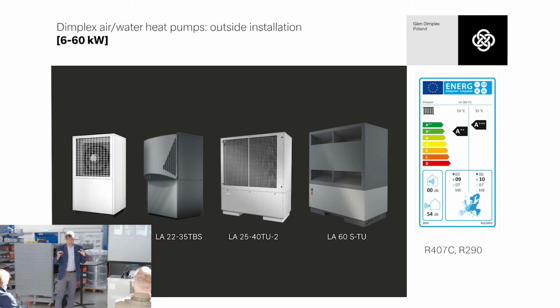Let's say something about the products, especially those dedicated to this purpose. It is not the whole range of the portfolio. The products I will show in the next slides are rather dedicated to heat recovery systems, and later I will show you some diagrams with these products, and everything will be clear. What we have at the moment for the heat recovery system, not typical, is a range of air-to-water heat pumps, especially larger machines from LA 25 to 60. That is the capacity of the device. These two ranges are dedicated to bigger houses or to such plants, such installations as you are interested in for heat recovery in retail stores. Also, we have some smaller devices in the range, but they are rather dedicated to single-family houses.